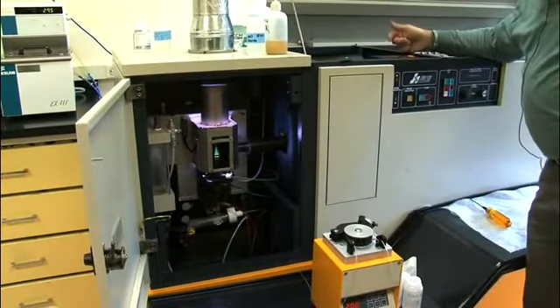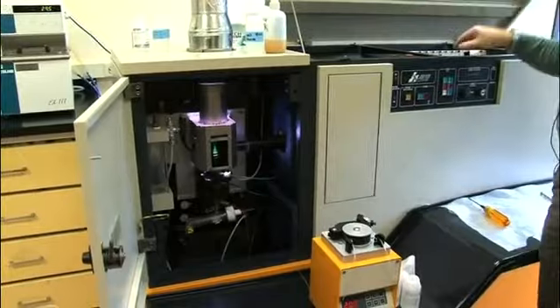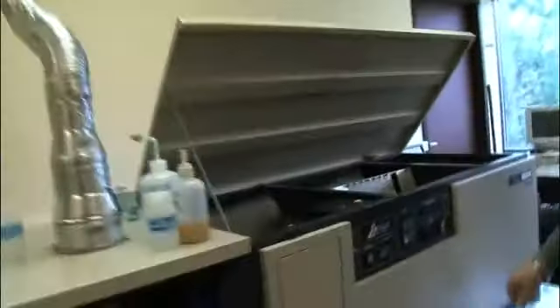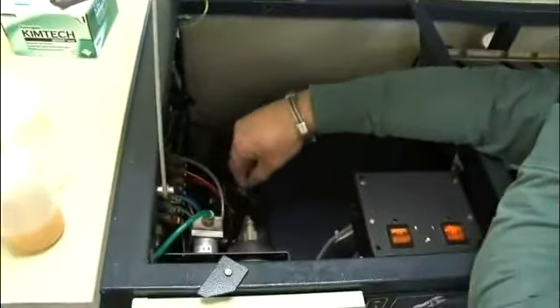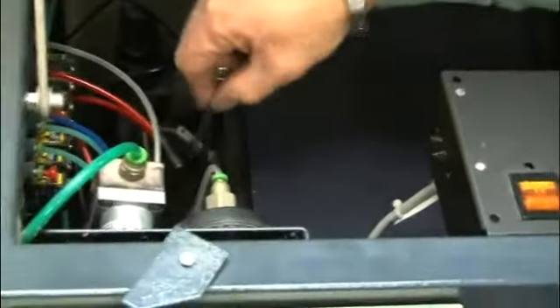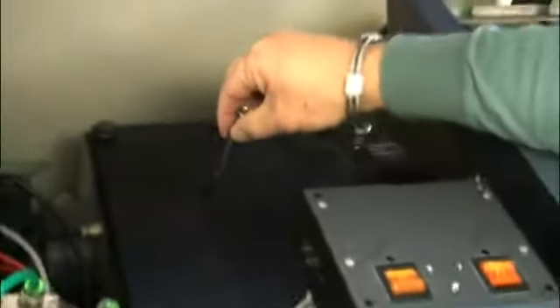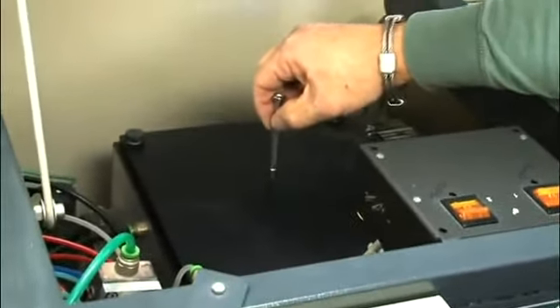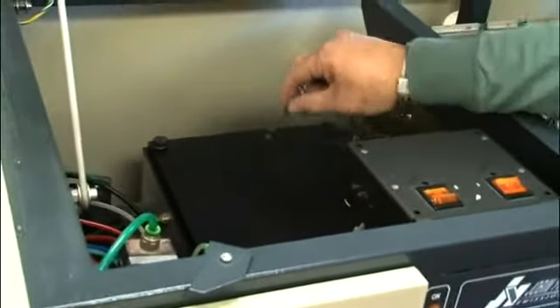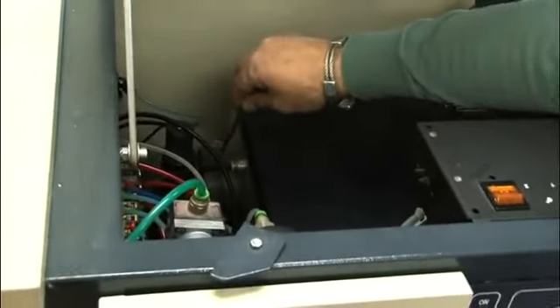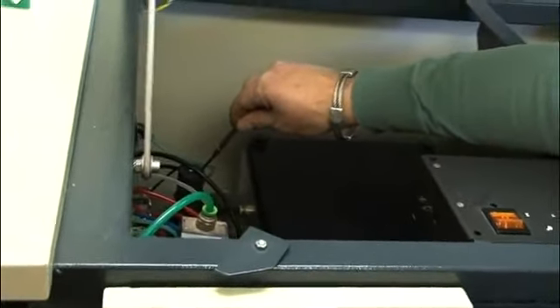So, I don't know if you can get inside here or if you need to get inside, but I can point things out just real quick. So down in here, your light comes in the optical path into this. This is a slit assembly. There are 2 slits in here that are controlled by the software, 10 and 15 microns. The light enters through the slit. It comes down this end to a mirror, which then bounces the light back to your holographic grating, which is here. The grating's job is to split the white light from the plasma into each individual wavelength. Once it does that, it sends that light to a second mirror down this end, and then back out another exit slit assembly, which is 15 and 80 microns, to this photomultiplier tube, which converts the light into an electrical signal, which goes out to the computer.